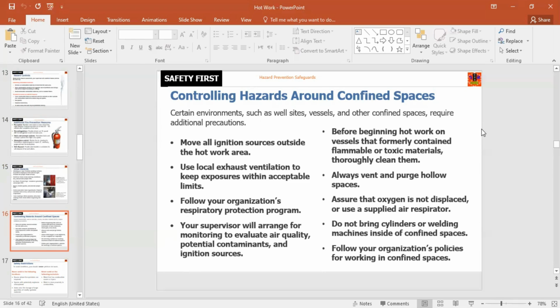Your supervisor will arrange for monitoring to evaluate air quality, potential contaminants, and ignition sources before beginning hot work on vessels that formerly contained flammable or toxic materials. Thoroughly clean them. Always vent and purge hollow spaces. Assure that oxygen is not displaced or use a supplied air respirator. Don't bring cylinders or welding machines inside the confined spaces, and follow your organization's policies for working in confined spaces by implementing a permit to work system.